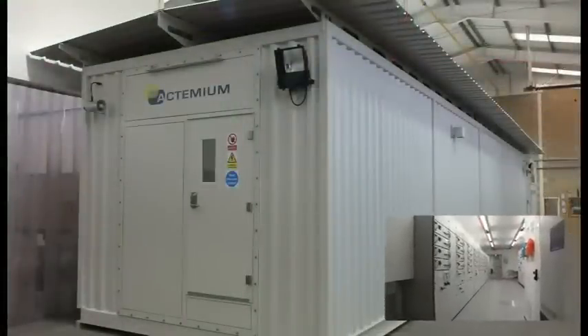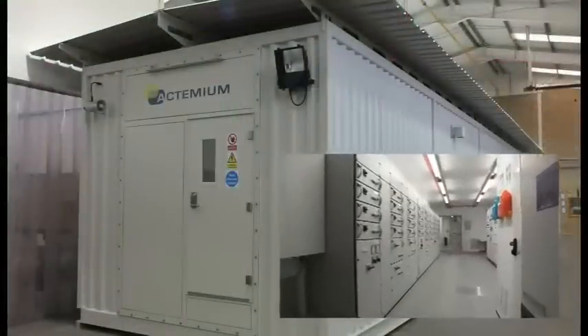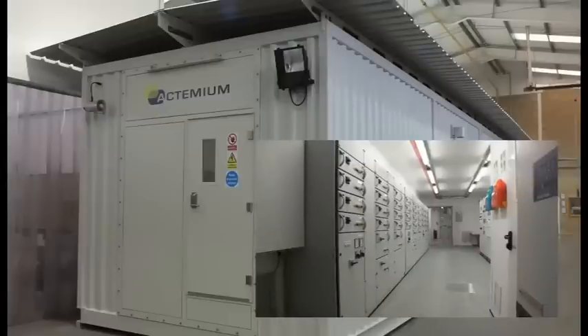Local equipment rooms are very popular in this type of environment. The benefits of such a room are obvious when compared with the huge cost of a traditional site cable installation, civil construction works and site testing and commissioning. The local equipment room is fully fitted out at our works, fully cabled, tested and commissioned as far as practically possible, allowing minimum installation and commissioning time at site.